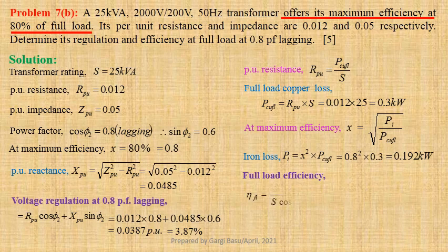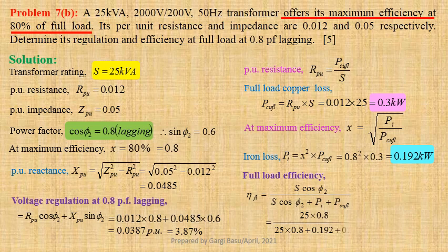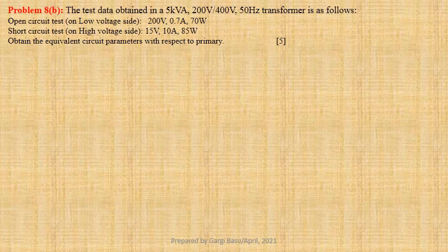Eta FL equals S times cos phi 2 divided by S times cos phi 2 plus Pi plus P copper FL. Using values we get 25 into 0.8 divided by 25 into 0.8 plus 0.192 plus 0.3. That gives us 97.56%.